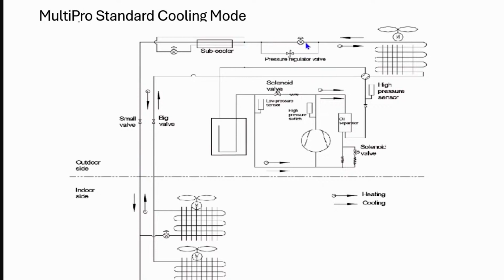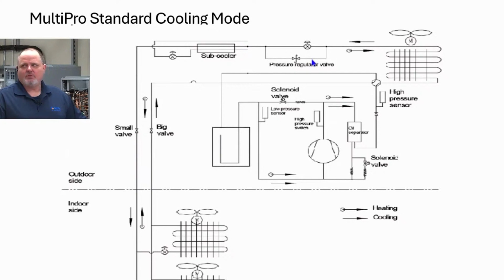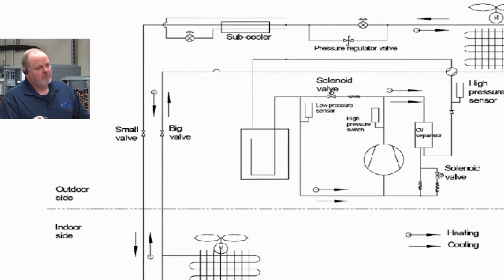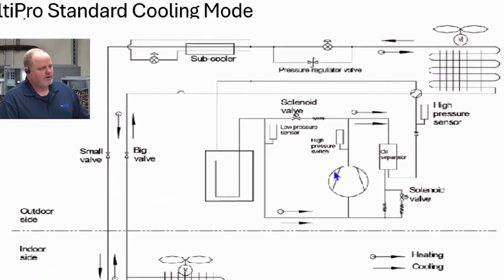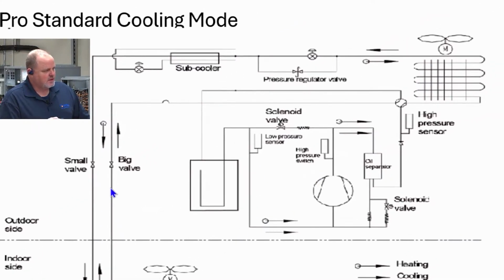So the EEVs in a MultiPRO system are from 0 to 480 steps. It's a little motor in there that drives the needle seat open and closed. When it's all the way open, we get free flow through it. If for some reason in cooling mode that EEV wasn't open, then we would be going into a pump down, because it'd be no different than if you took your small service valve and closed that thing up. Now we're going into a pump down, pumping all the refrigerant in the outdoor unit, and it stops between this liquid pipe right here, or liquid valve right here, backs up all the way into this coil, up to the compressor.